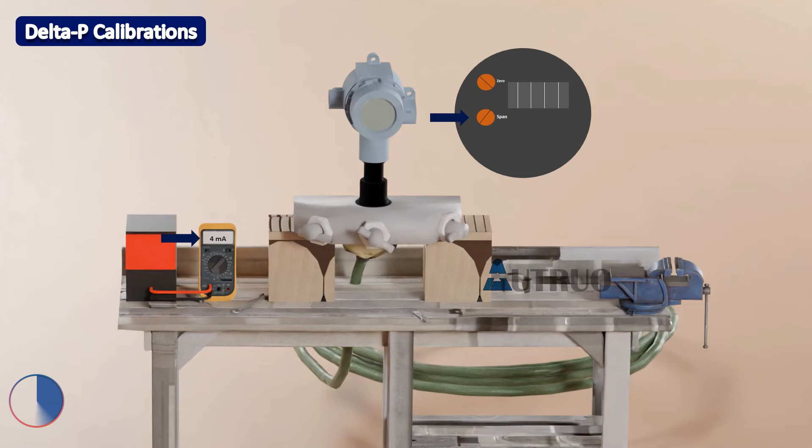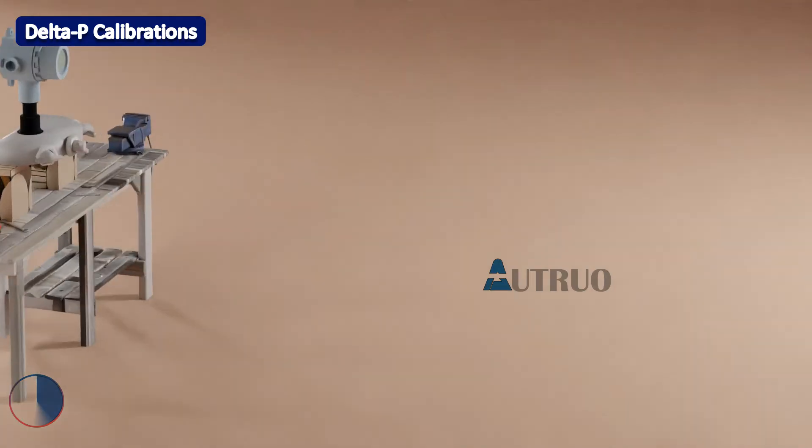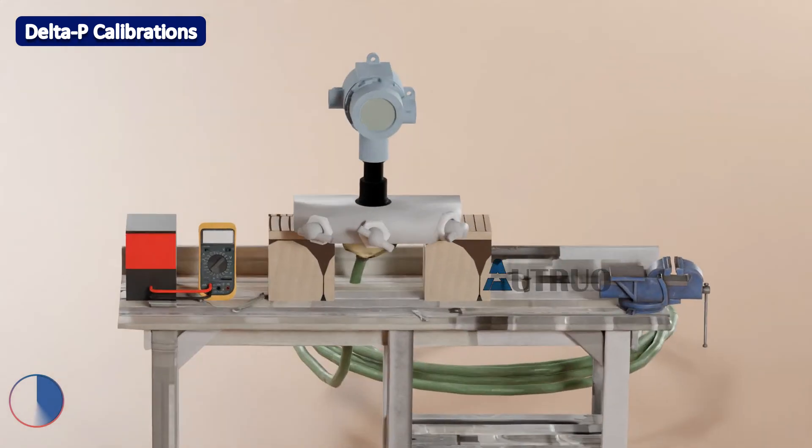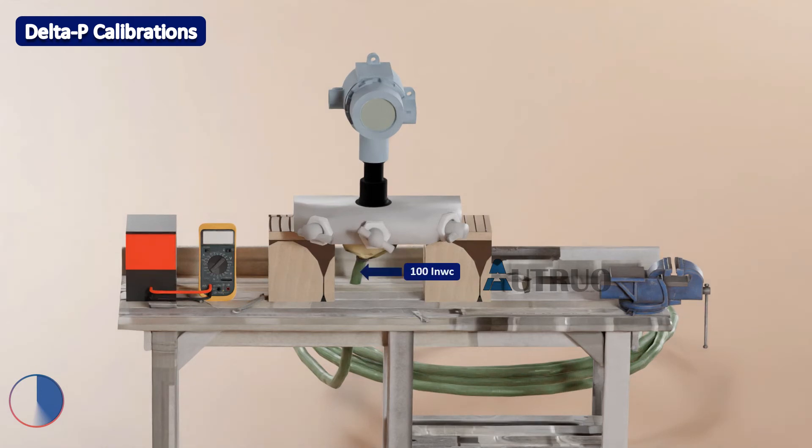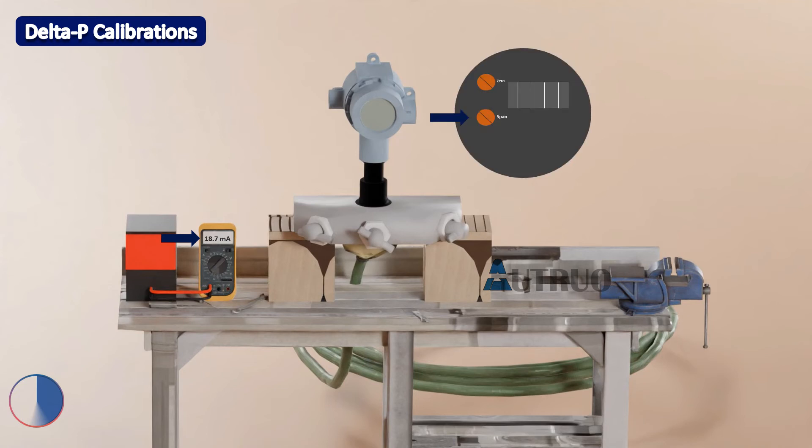Now let's calibrate the upper operating limit of the transmitter. The equalizing valve will be varied in such a way that the pressure supplied will only be supplied to the high side of the transmitter. We will now need to apply the pressure that is equal to 100 inch of water column to the transmitter. Now the current coming from the transmitter is 18.7 milliampere. We will now vary the span until the transmitter levels up at 20 milliampere.